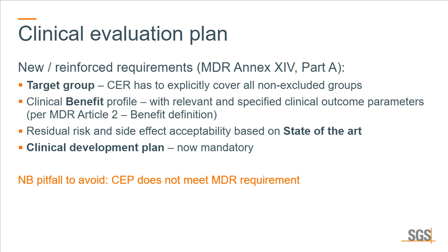So previously, we have seen where manufacturers intended the device to be used, or at least did not exclude the use, or did not indicate in the contraindications certain groups that typically require special consideration, like pregnant women, lactating women, children of different age groups, elderly patients, or anything like that. And this now has to be explicitly addressed.